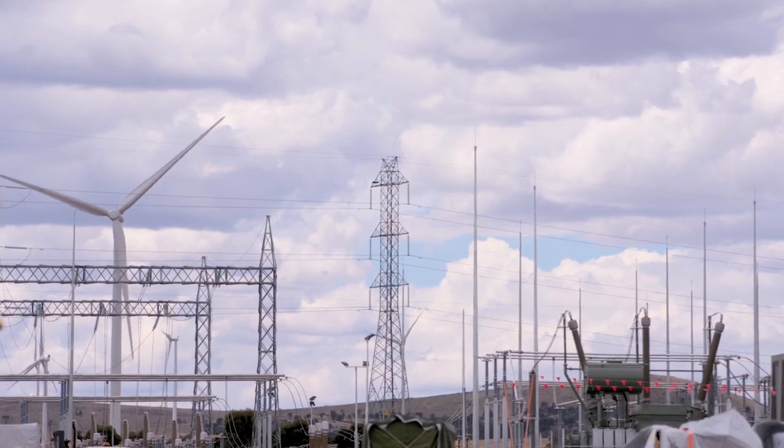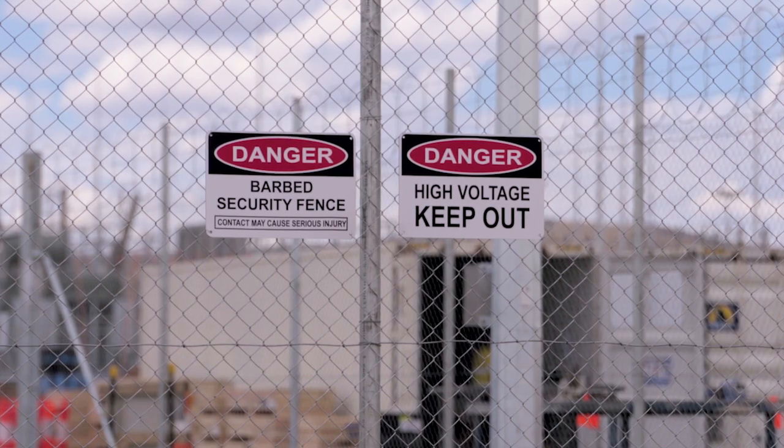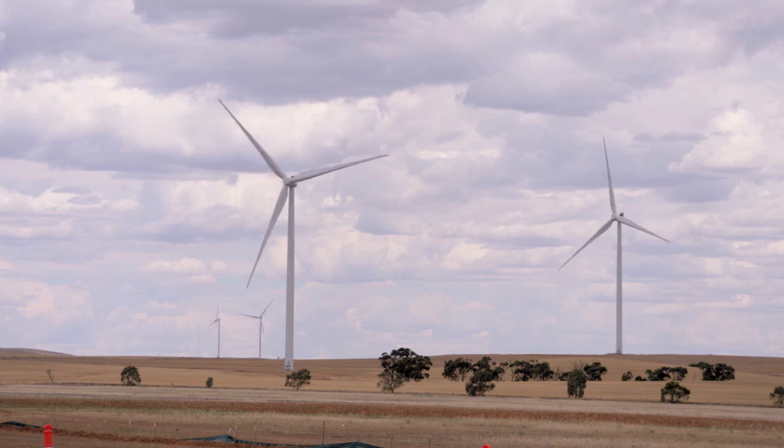It's definitely an exciting and innovative project. There's definitely a sense that new ground is being broken. Large-scale storage has been talked about for a long time, and this is the first implementation of that. This particular project has an energy storage capacity of 129 megawatt-hours, and it can discharge at 100 megawatts. That capability will help at times of peak demand, and there are also some other benefits that we'll talk about a bit later.